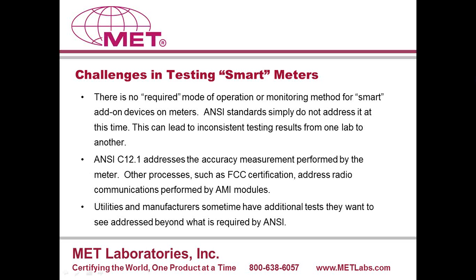So we were talking about the challenges, of course, in testing smart meters, because the standard does not necessarily have specific requirements for smart meters per se. It really was developed from the older electromechanical style revenue generation meters. But now everyone that has a metering product wants to refer back to the ANSI C12 test requirements for any type of metering product, really. So we see all sorts of products that are not necessarily revenue generation meters that are required for testing by the buyers of that product or the potential buyers of that product.